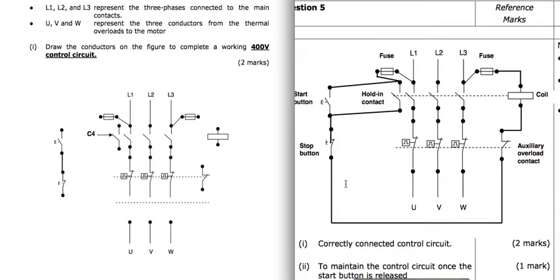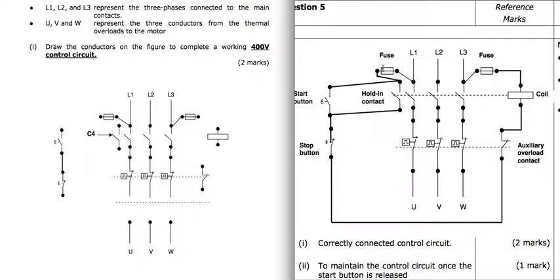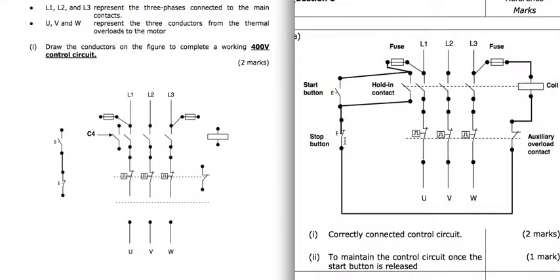So how are we going to connect that up? We're going to have L1 feed that fuse and feed the start button. Now I would have taken mine from the fuse straight to the start button there, and then the holding contact in parallel with the start. But it's exactly the same operation whether you take it there or there. So the main essence is that this holding contact is in parallel with this start button, and the stop button is in series. So we go through the circuit, through the stop, through this overload contact, to the coil, through the fuse, to the L3. So the control circuit is across 2 phases. It's across 400 volts there. If we press the start, we'll get the feed through to the coil. Close these contacts, motor starts, held in by this holding contact.